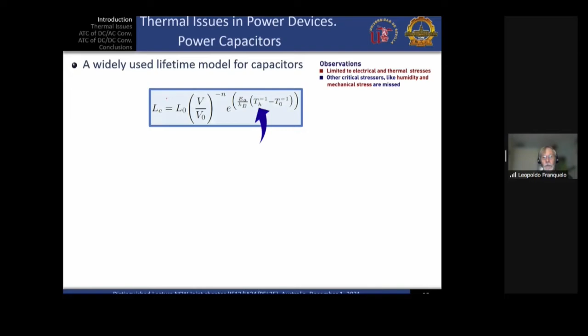Then how can we know this temperature? We can do something very similar to estimate the temperature, taking into account the losses, the thermal resistance that should be a data from the manufacturer, and the ambient temperature. So we can see the increase in temperature, and we can calculate the power using the current. But as the ESR may depend on the harmonic, we have to do the summation of all of them, the total power produced by each of the harmonics in the current flowing through the capacitor. So we need to know the current through the capacitor.